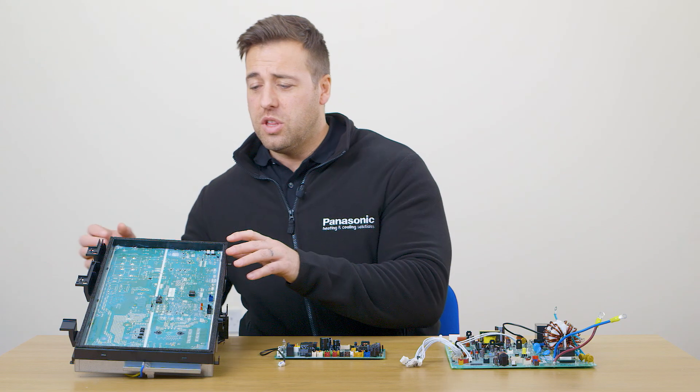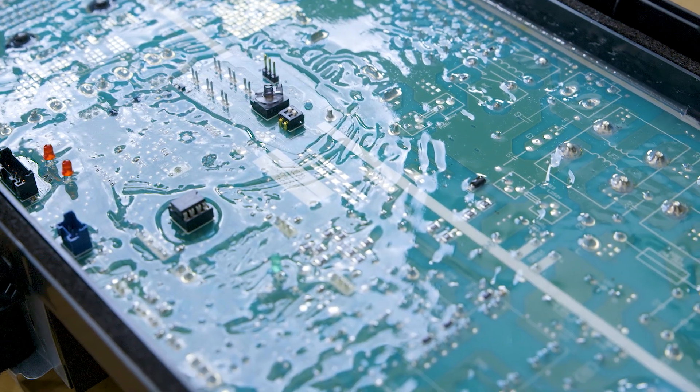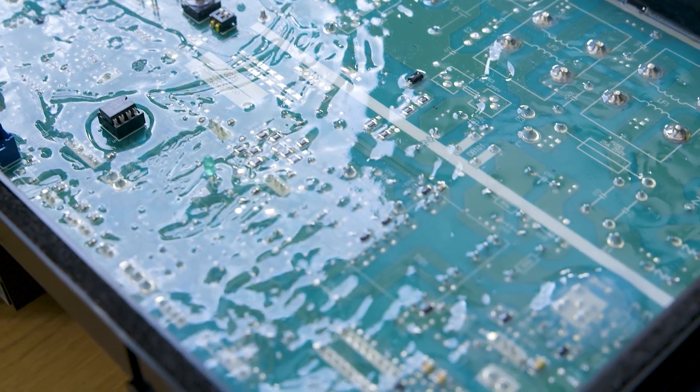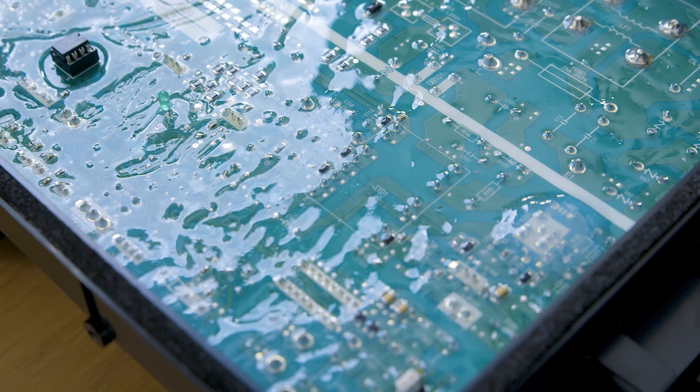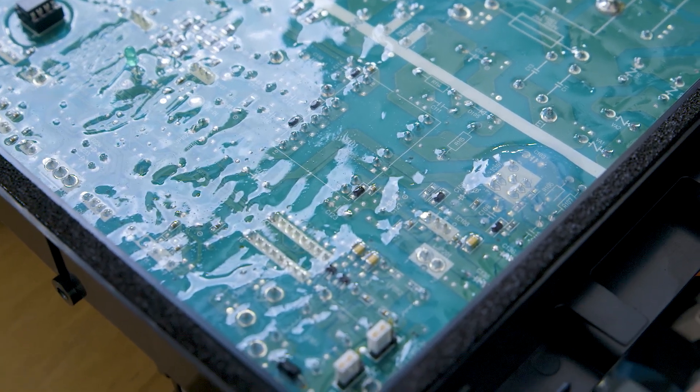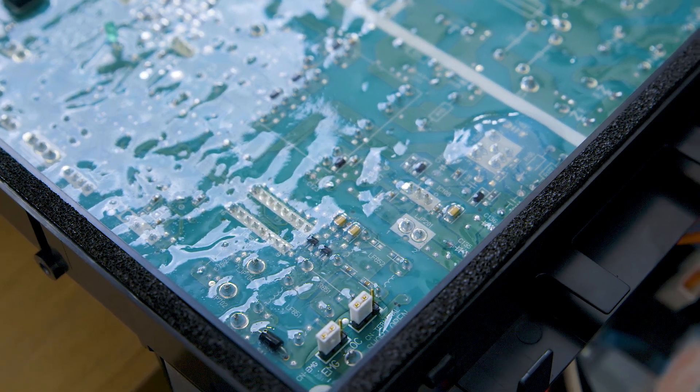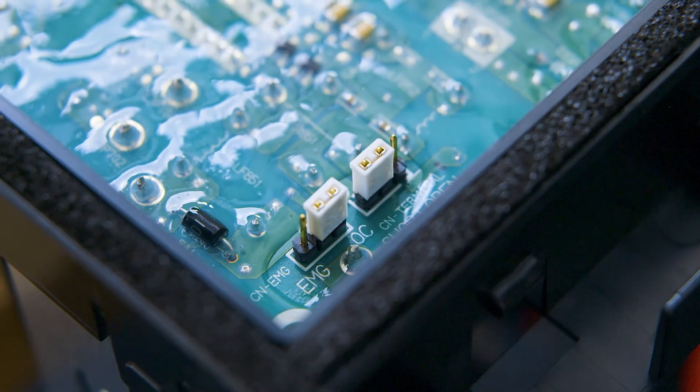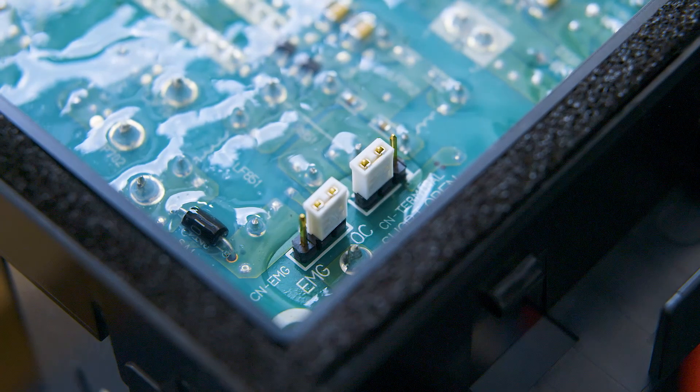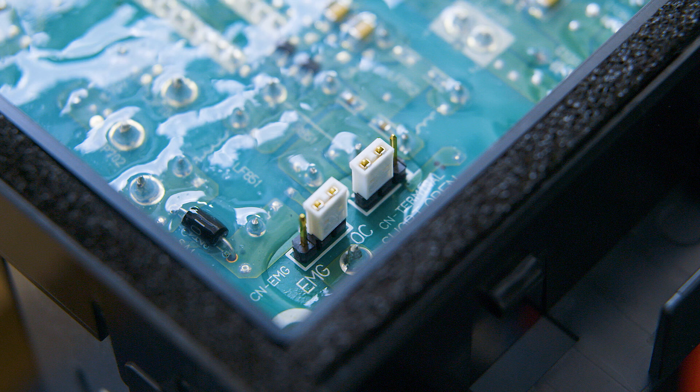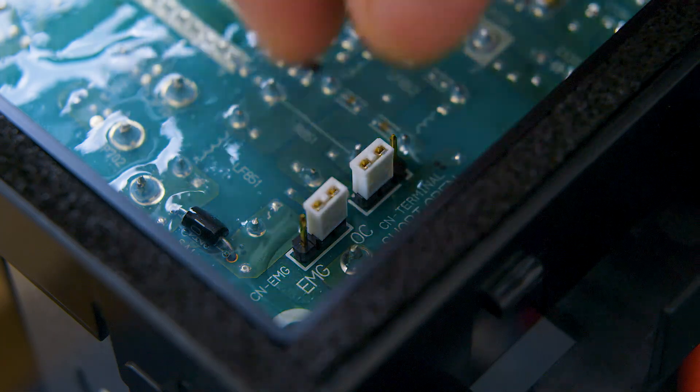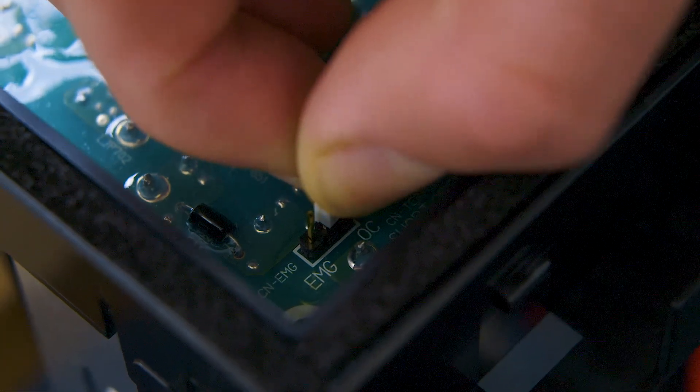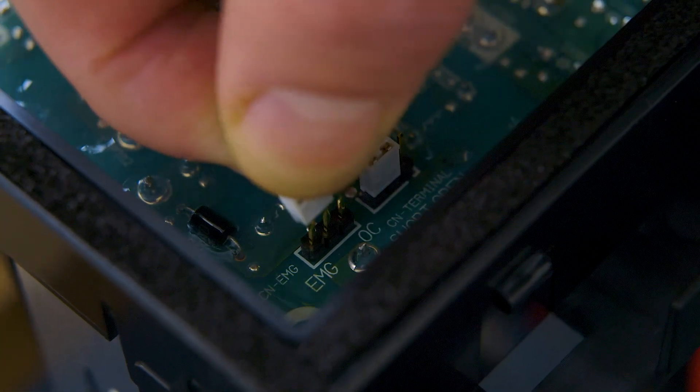Moving on to the other outdoor PCB, the one that is upside down. There's no plugs on the back of the board, so we can't access them while it's live. In the bottom corner you'll have a jumper plug with three pins. The jumper plug will be placed across the two pins labeled OC. Simply unplug and plug across the two pins labeled EMG.